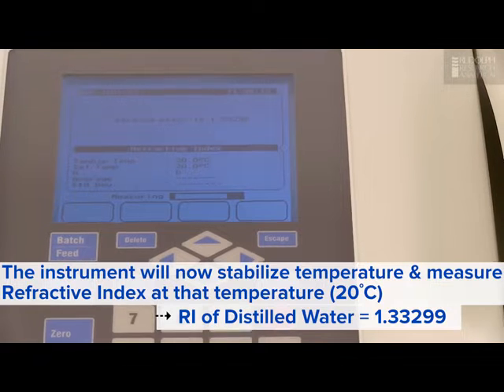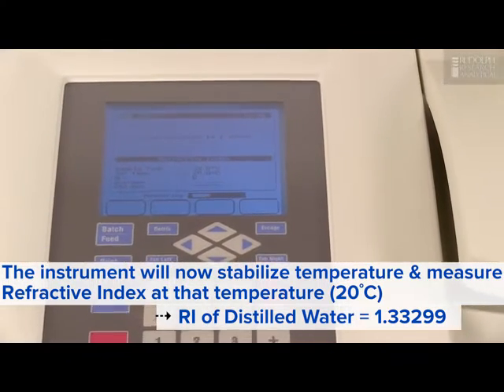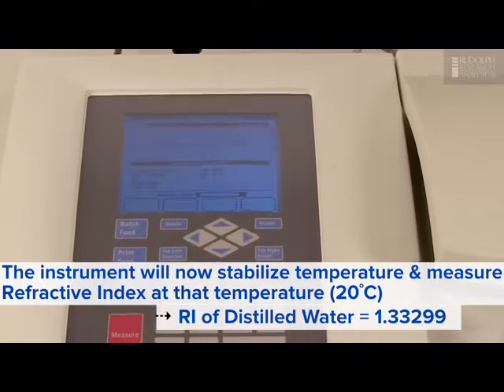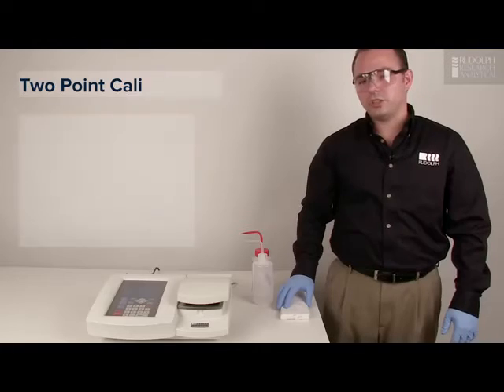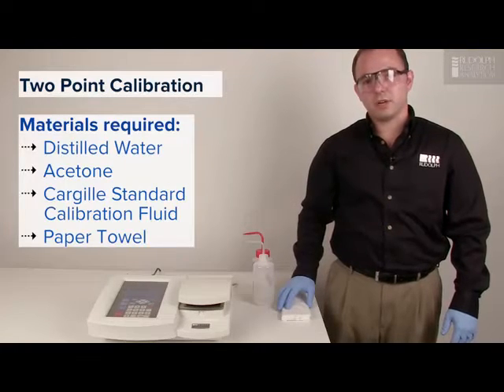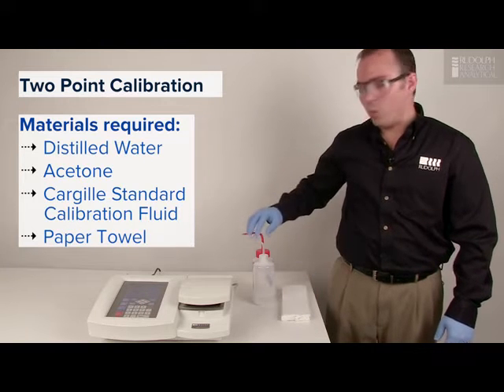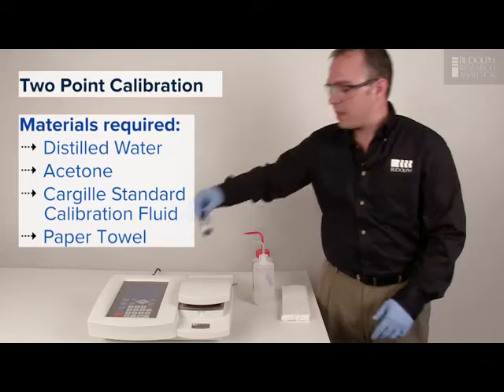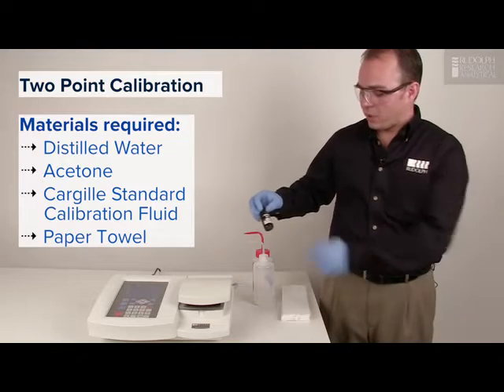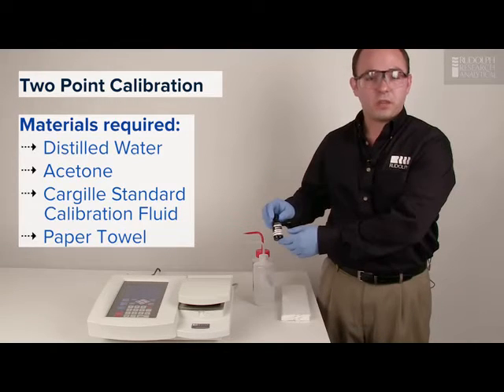After you press the Done key, you're going to see the system stabilize temperature and the measurement bar is going to be going across the screen. Once it's completed and measured the water, it's going to adjust the refractometer to whatever refractive index at that temperature. Now that I showed you how to perform a single point calibration, next I'm going to show you how to perform a 2-point calibration using water, acetone, and a Cargille standard at 20 degrees that's usually supplied with the refractometer.